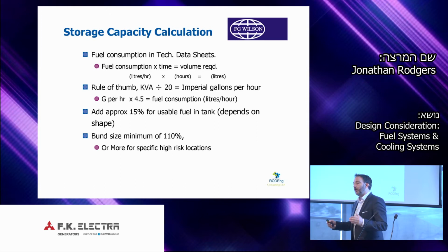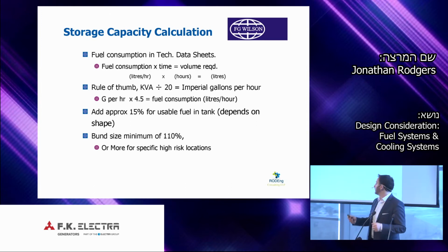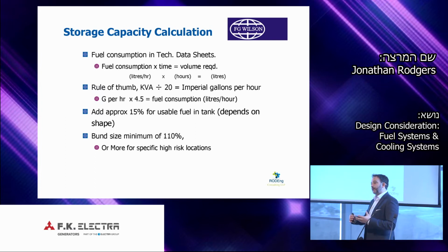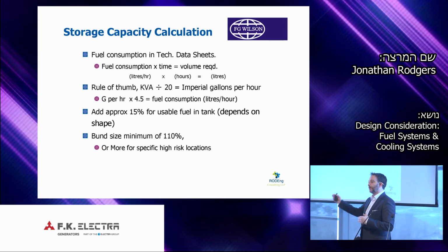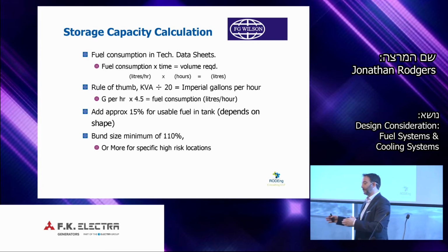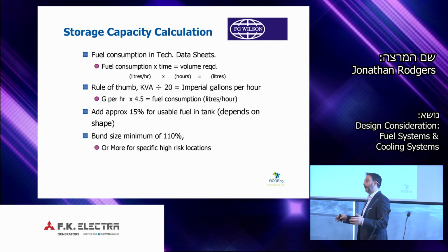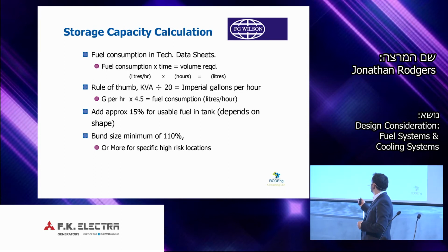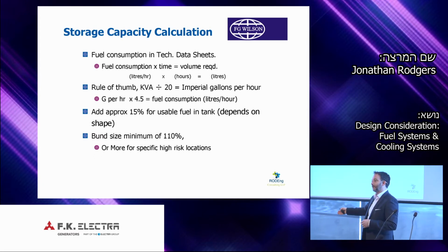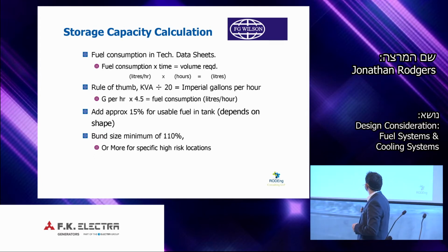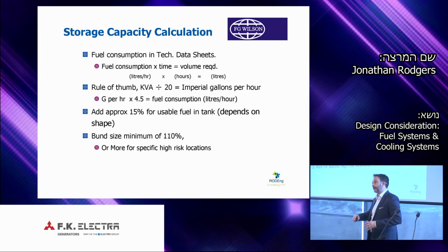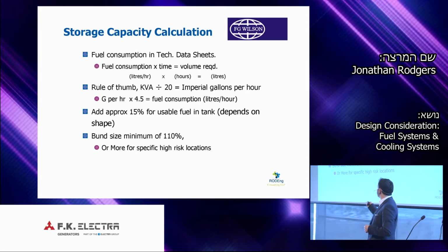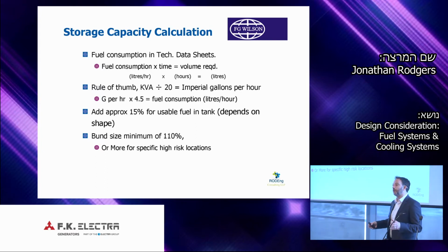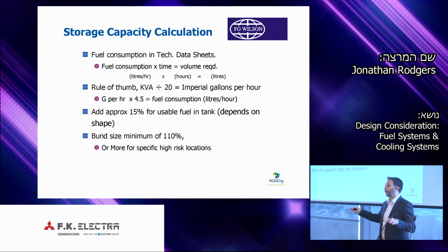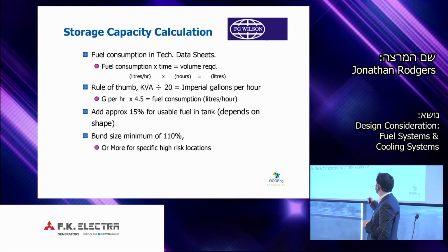When sizing the tank, we have to consider allowing for additional volume within the tank. From a design perspective, it's approximately 15% additional volume. So if we need to have 1,000 litres of fuel for supply to the engine for autonomy, the tank will need to be 1,150 litres, 15%. So also we look at bunding. So this is spill containment and bunding. And the bund size itself should always be a minimum of 110% of the volume of the tank. And this is of the total volume of the tank.